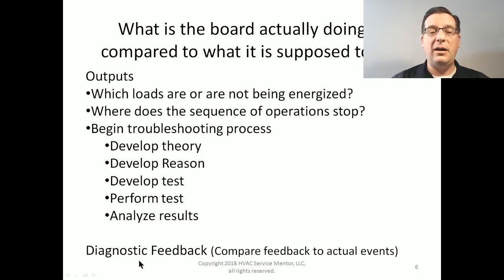So not only do we need to look at the diagnostic feedback and understand it, we also need to verify that it is in fact true. In the event of a control board failure, one of the failure modes can be that it is giving false diagnostic information. For example, that pressure switch could very well be closing, but the control board for some reason is unable to recognize that because of its failure, and it's going to tell you that it's not closing. So in the event that we have a pressure switch issue, we need to verify that the pressure switch is or is not closing before we do anything else. If you have diagnostic feedback, always confirm that it's actually happening before you do anything else.